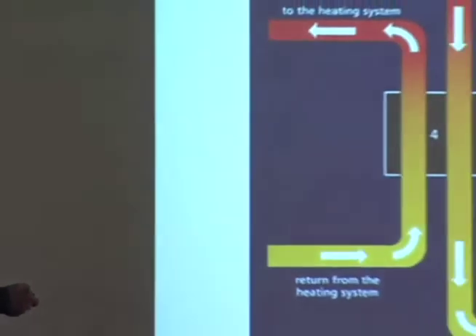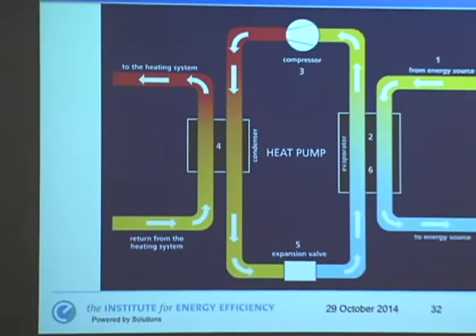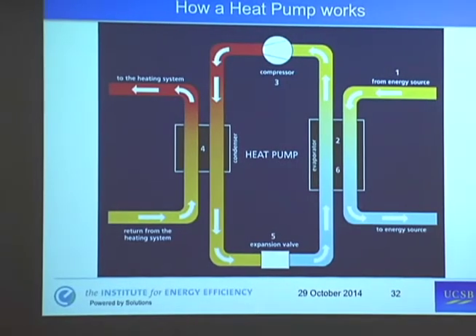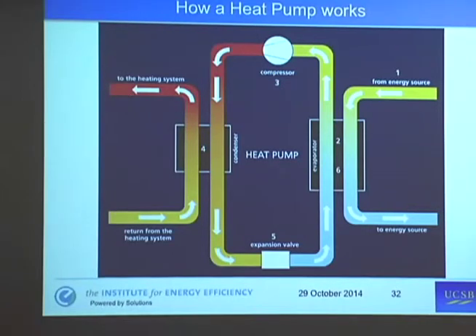This is basically the principle of what Stanford is doing. They'll have many special heat exchangers with an intermediate loop and a compressor that takes a refrigerant gas, compresses it, and generates heat, which is then exchanged through a heat exchanger and an expansion valve that cools the gas and delivers cooling elsewhere. So they're coupling their heating and cooling systems, saving a huge amount of energy.